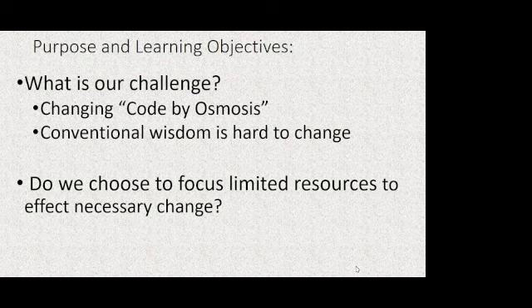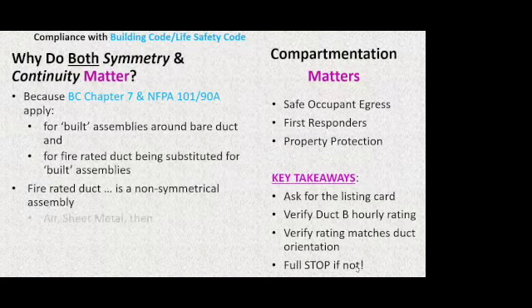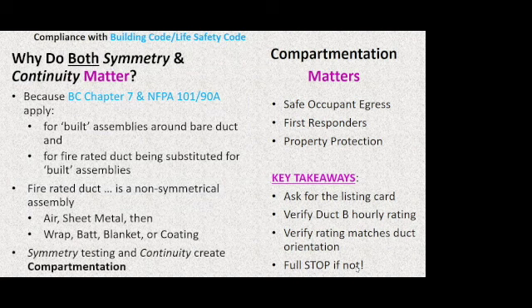And all it takes is for one person at the beginning of that chain to miss something like this duct A, duct B thing when it first comes out, for that mistake to get propagated for years and years and years. And the consequence is that we don't have compartmentation. We have compromised everything from penetrations to entire runs of what are supposed to be shaft equivalent duct work. We omit dampers that we've not got equivalent protection for, alternative protection for, and so we are compromising the safety of the occupants, the expectations of performance for the first responders, and most certainly have not provided the property protection due the owner for a proper code complying structure.